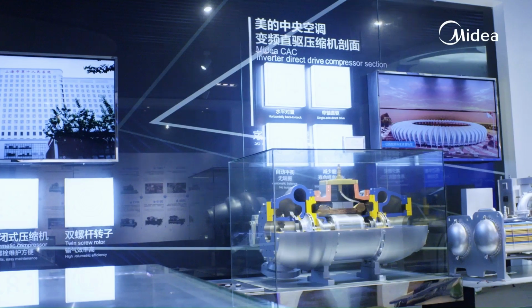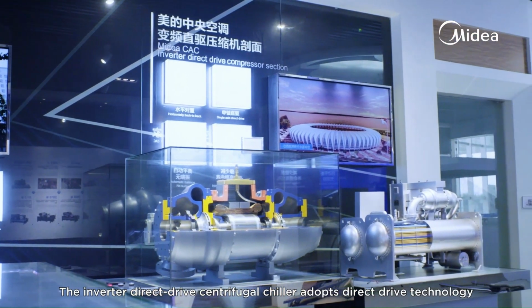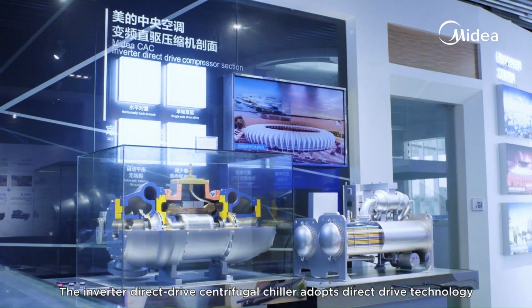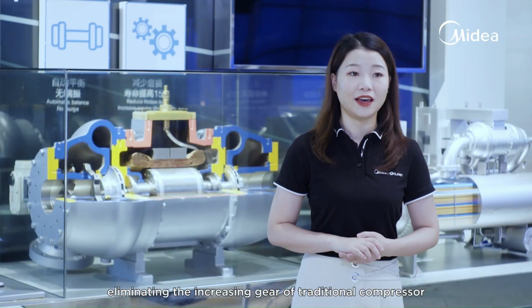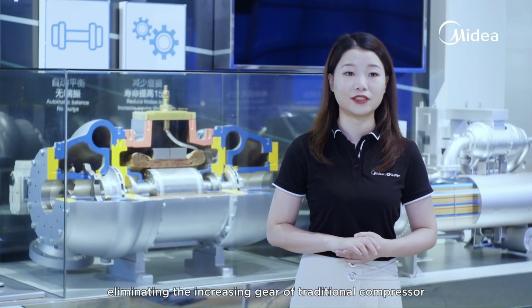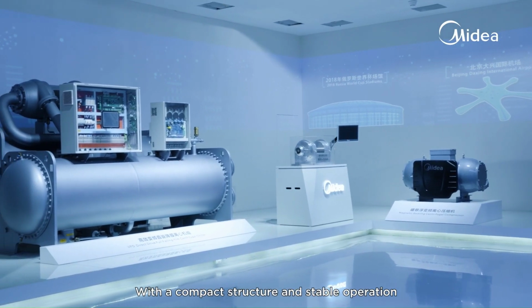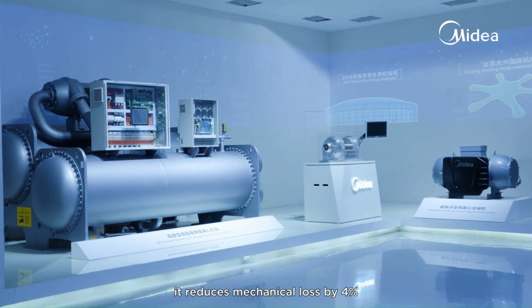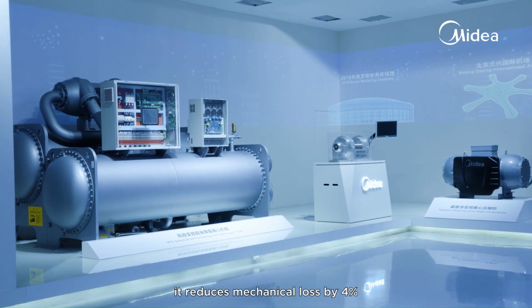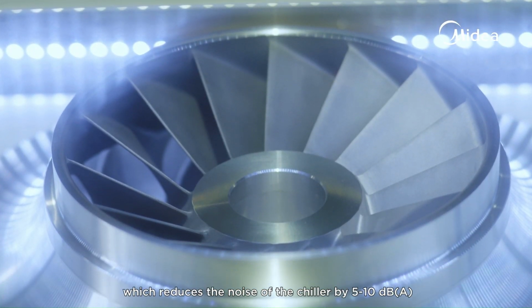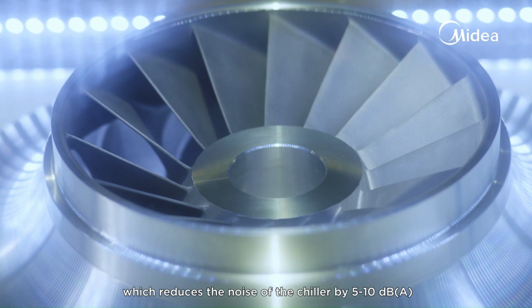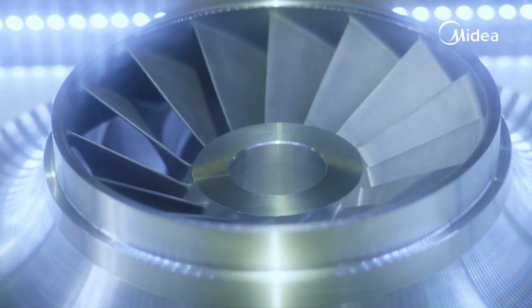The inverter direct drive centrifugal chiller adopts direct drive technology, eliminating the increasing gear of traditional compressor. With a compact structure and stable operation, it reduces mechanical loss by 4%. No gear high-speed motion, which reduces the noise of chiller 5 to 10 dBA.